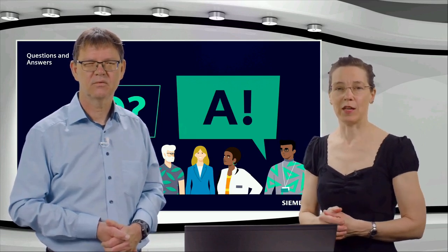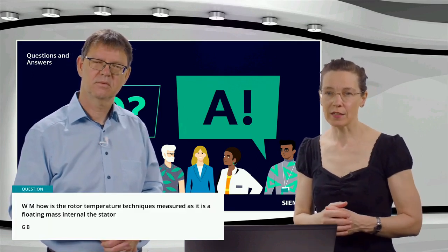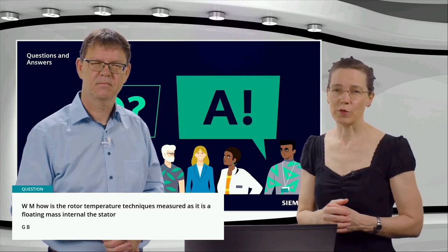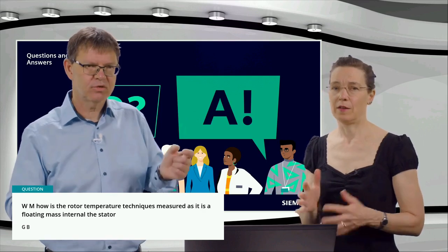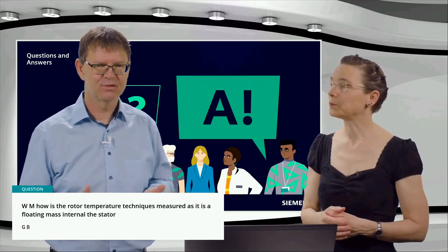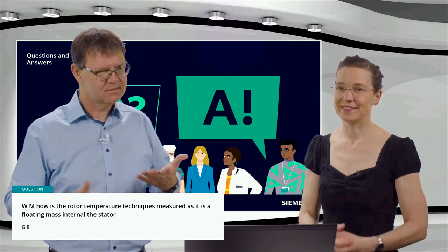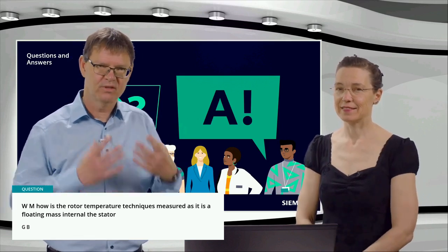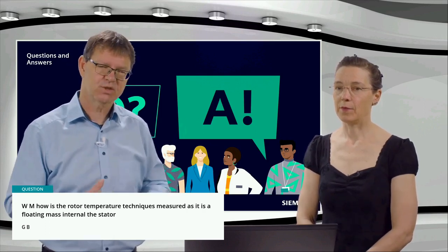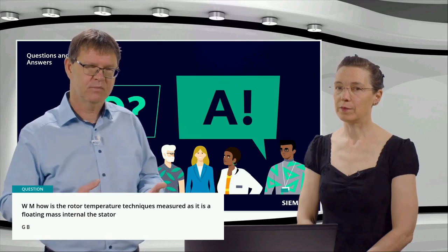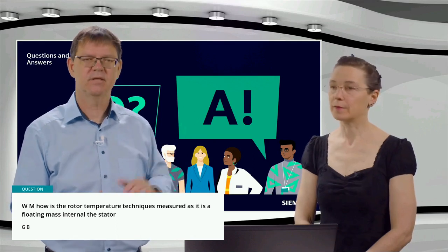Then the next question came in from WM. How is the rotor temperature measured, as it is a floating mass internal to the stator? Okay, so we don't have a sensor in the rotor, maybe you mean that the rotor is rotating. We just take the currents which go into the motor, the three phase currents, and with the data from the motor manufacturer, we build up this thermal model, and this thermal model we use to estimate the temperature.